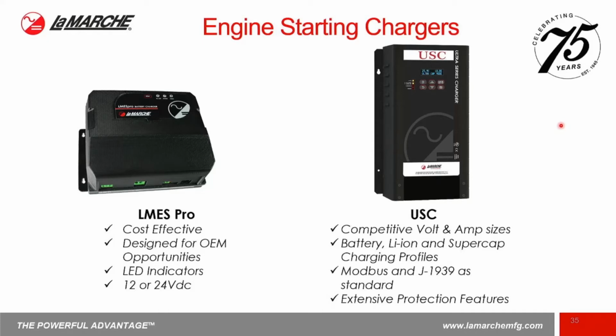Compared to the USC, where you do have much more competitive sizes as far as voltage and amp, so you can actually go with a 12, 24 volt. We do have some more voltage ranges allowed, obviously not for the engine starting market, but we do offer a much higher range of amperage sizes. Obviously, the big factor for the USC is that you can charge much more than just your lead acid and NiCad. You can charge lithium-ion batteries and your supercaps with all adjustable profiles. And your standard Modbus J1939 feature is very important to us. Again, we have to reiterate that.